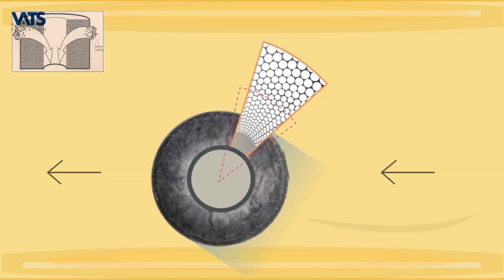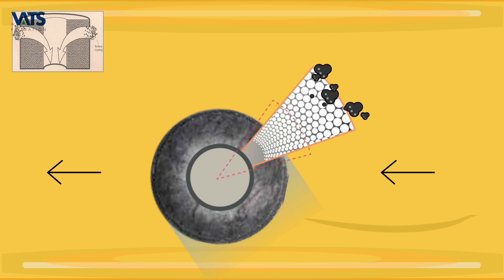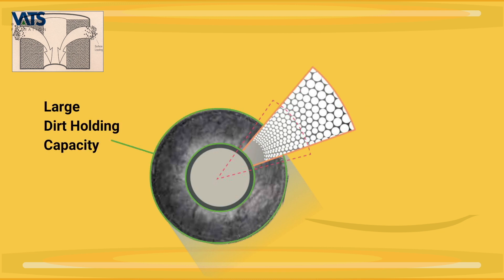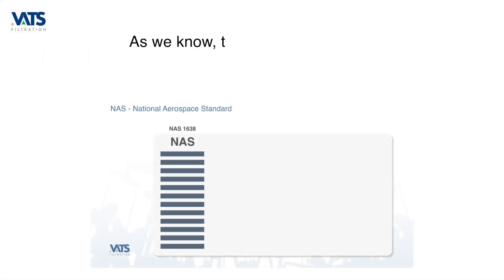While the larger particles are trapped in the outer layers, the smaller particles keep going down towards the center. This means that particles across the whole range of size distribution get trapped at different depths across the filter, so the filter now has a large dirt holding capacity while absolutely not sacrificing on efficiency.